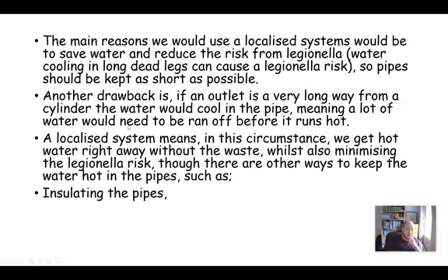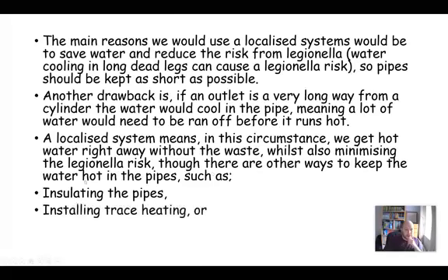And yeah, the big benefit of the localized systems means we get hot water straight away without any waste, whilst minimising Legionella risk. But we can help minimise the risk from Legionella if we did use a centralised system by insulating the pipes. All 15 and 22mm pipe work over 12 metres long on hot water systems should really be insulated.